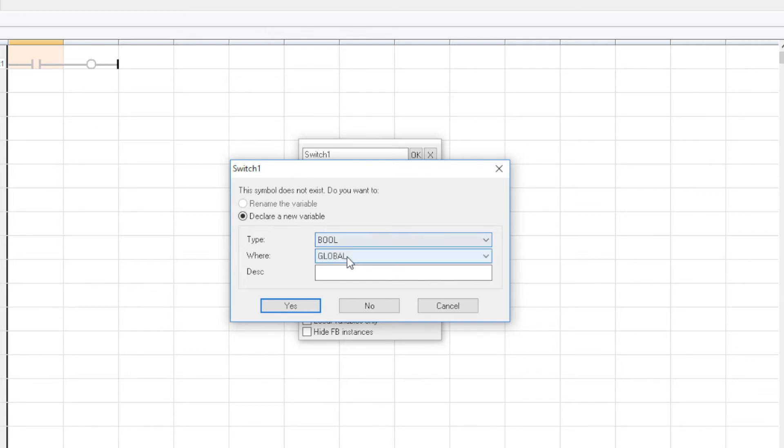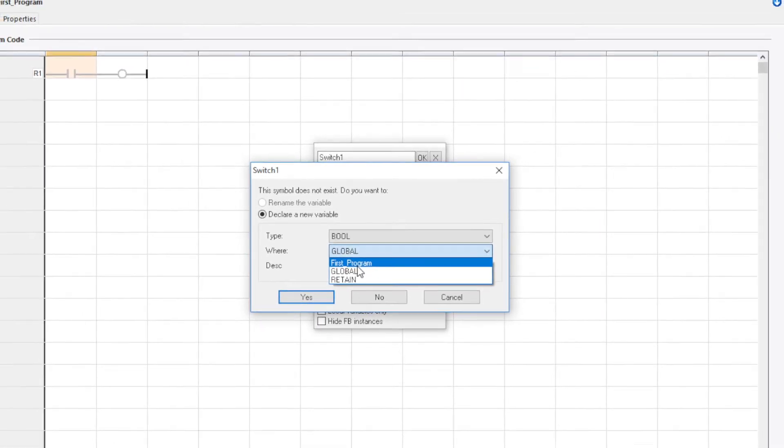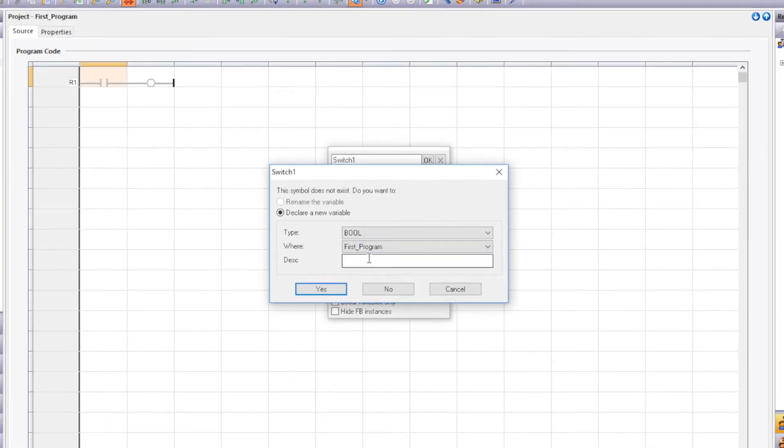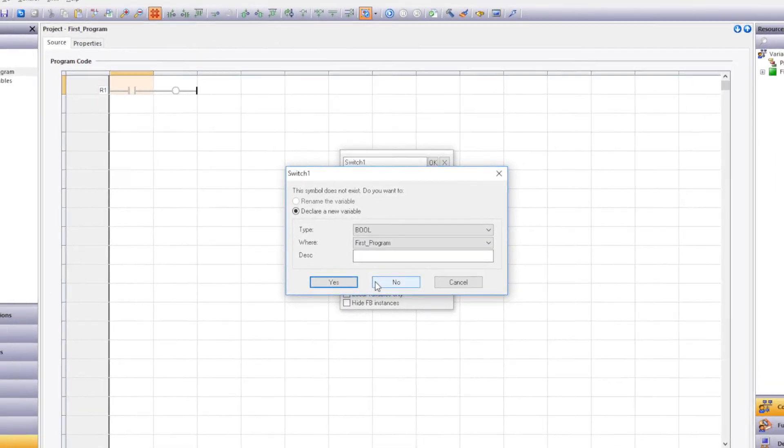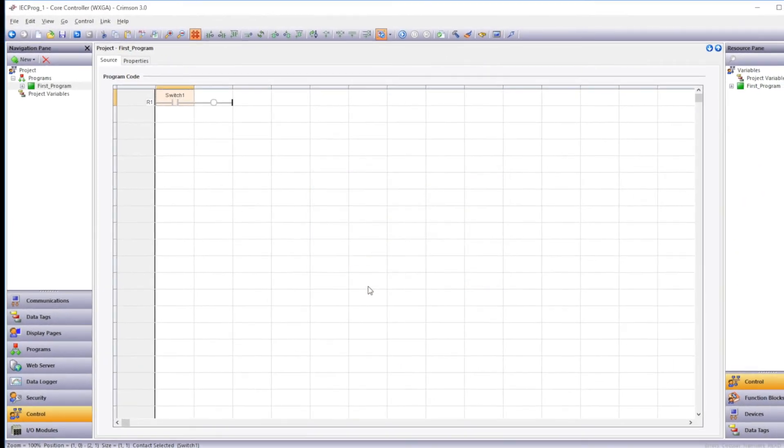Where is the dictionary that the variable will be stored in. The global dictionary can be accessed by all the programs in Crimson Control. The first program selection there is the local dictionary. So these will be variables that can only be used by the program that you're storing it in. So that's what I'm going to select here. Selecting the retain dictionary will allow the last known value to be restored on a power cycle. The description field can allow you to add a little bit more data about that variable. Click yes.